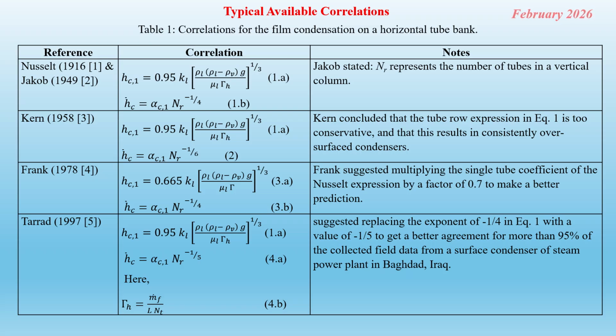Jakob in 1949 based his correlation on single tube condensation on a horizontal tube as presented by Nusselt in 1916, by adding the effect of condensate passing from one row to another, which reduces the overall heat transfer coefficient because the condensate covers more surface area and adds resistance to the condensation process. At the surface of the rows after the second, and going to the third, it becomes more difficult, and the heat transfer coefficient becomes less, and so on.